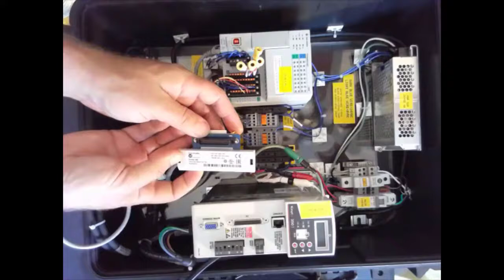Here we have our I/O connector. This is tied to PLC outputs that feed inputs to the servo, like registration, home, and over travel switches. Make sure you're very careful because this is a very small connector with delicate pins. We're just gently going to push this in here straight on and kind of wiggle it down, and there it goes. We don't have to screw it in, it's a pretty tight fit.